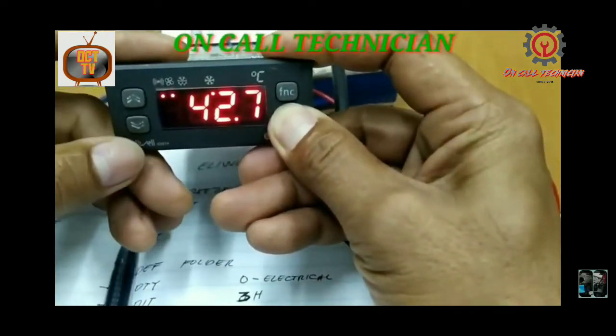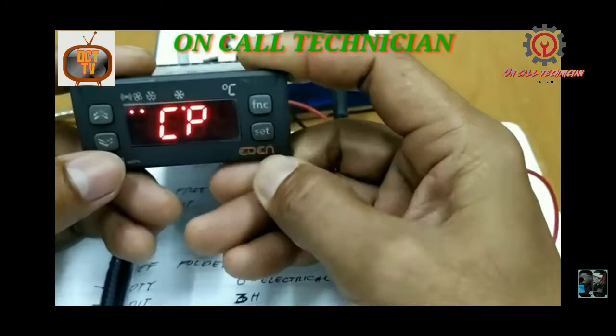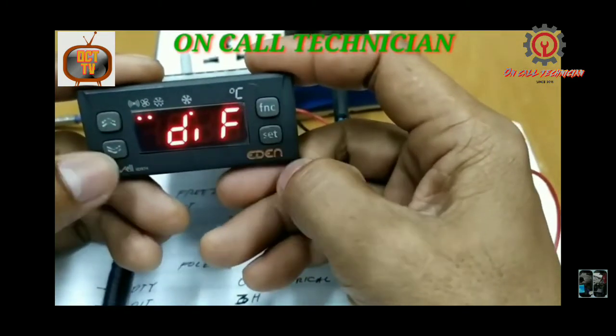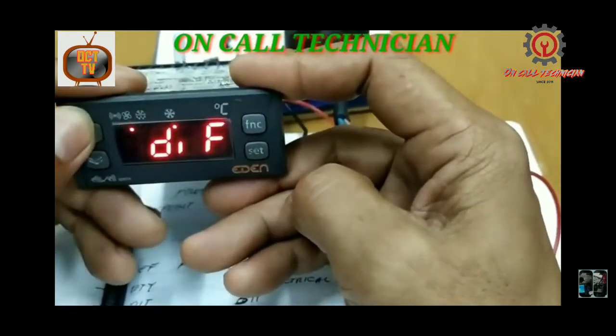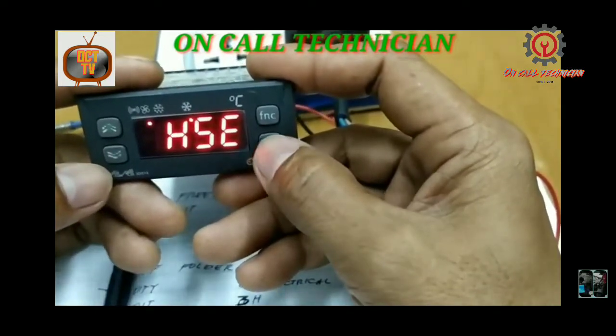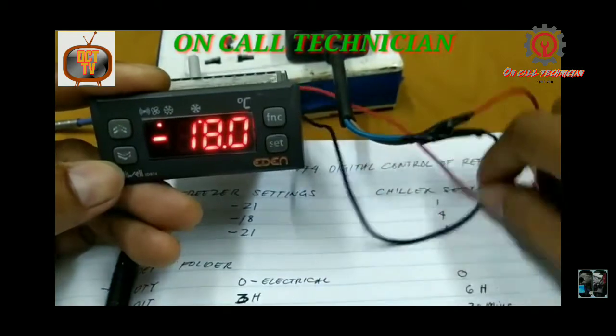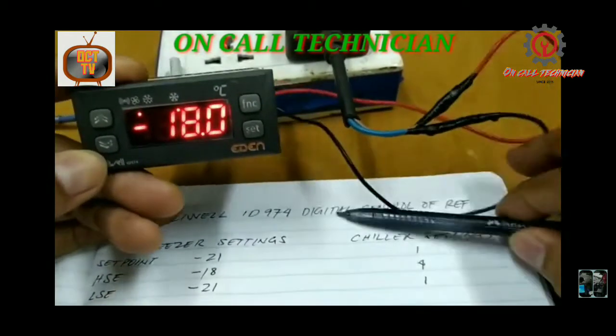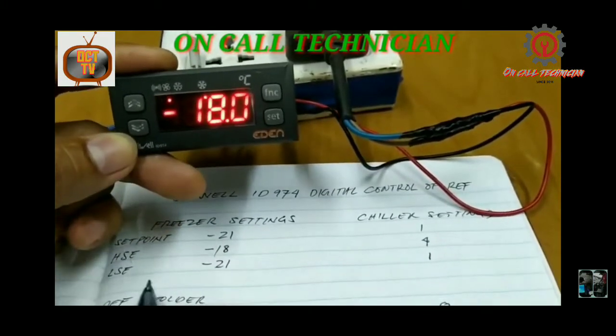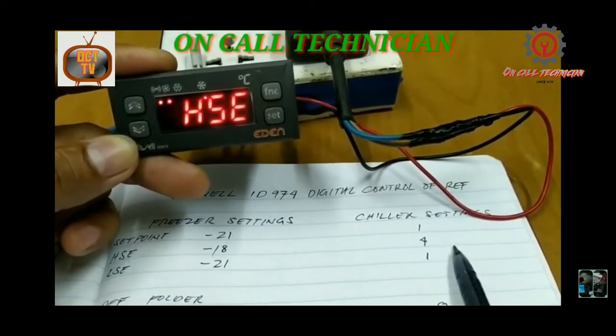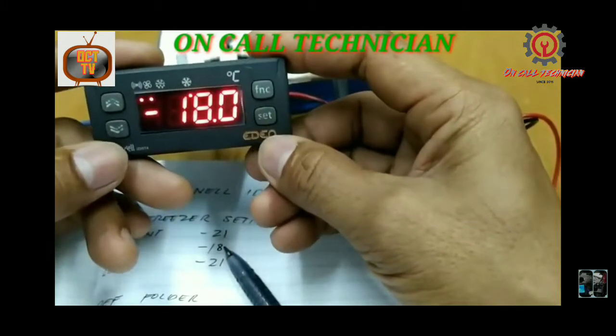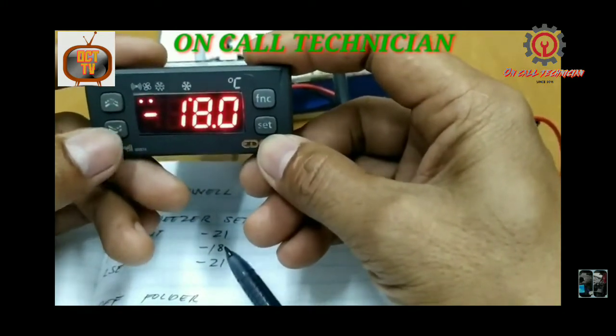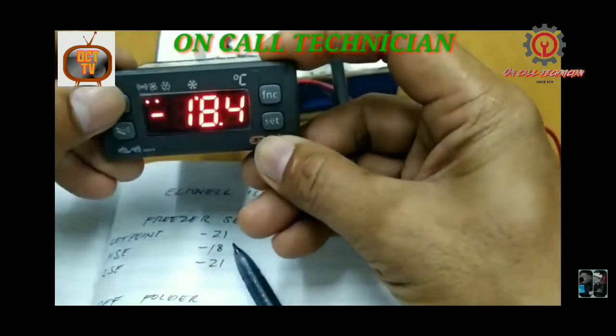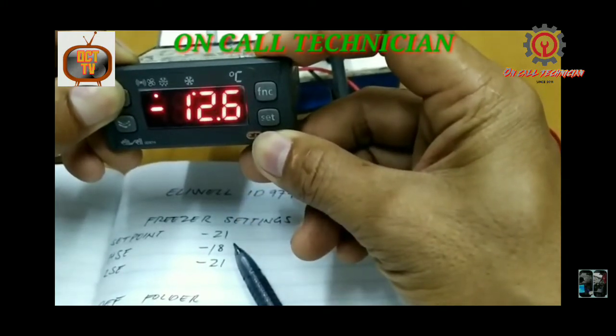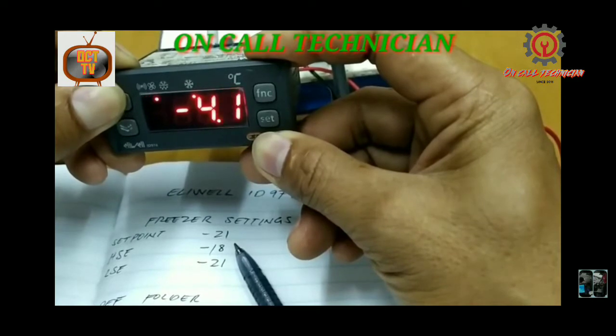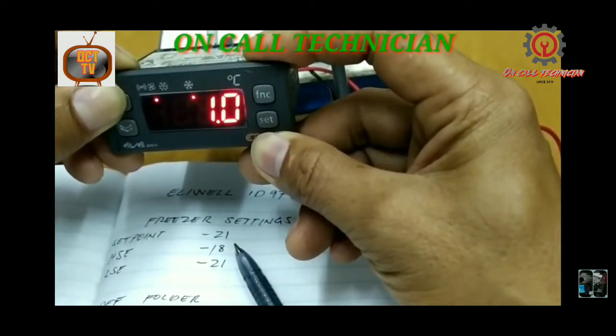After 15 minutes of inactivity, the control goes back to the display. Just press the set button. The differential we already set to 3 degrees Celsius, and for HSE, as I press the set button, the value is -18. So -18 is the freezer setting, and we're going to change that to +4 for chiller setting, since the currently installed is a freezing setting. We are going to change that to chiller setting, so just press the up button and you see it's going up from -18.